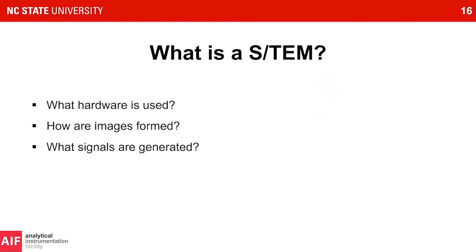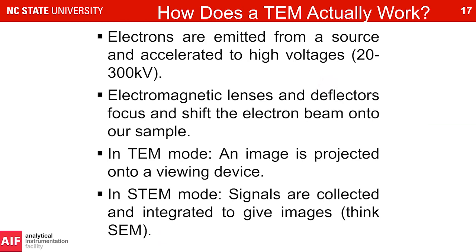What is a scanning or transmission electron microscope? In brief: we have an electron source — which determines the microscope's performance — we generate electrons and accelerate them to high voltages, somewhere between 20,000 and 300,000 electron volts. We use lenses and deflectors to focus and shift the electron beam. In TEM mode, we generate an image and project it onto a viewing device. In STEM mode, we raster a very small probe over our sample and generate signals that we integrate to form images — operating much like an SEM.